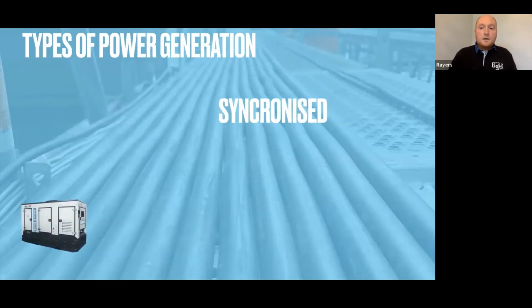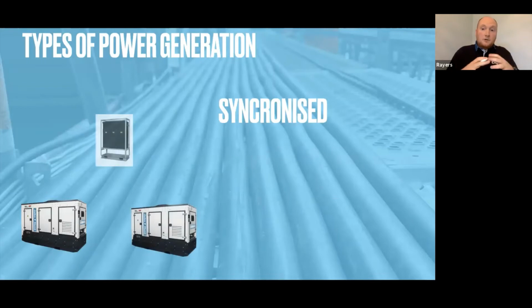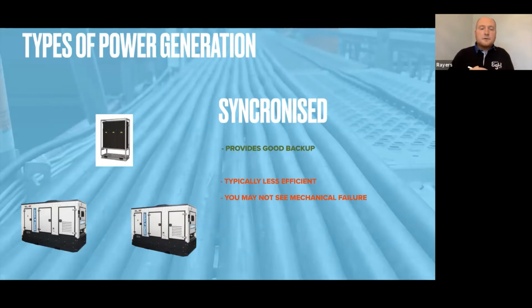Thank you. So perhaps a slightly more reliable way of working this would be to use what's called synchronized, and that's whereby both generators run simultaneously and they both cable into what's called a common bus or a distro board, which you can see above there. The cables run to that point, and then you put a communications cable between the 2 machines, and the control panels map what the generators are doing, and they essentially ensure that they're doing the same thing. This system provides a really good level of service and no interruption in the event of mains failure.